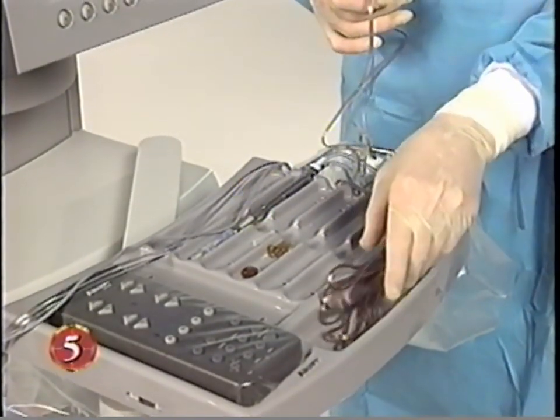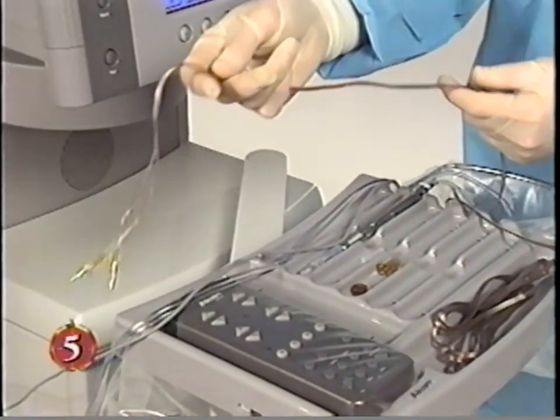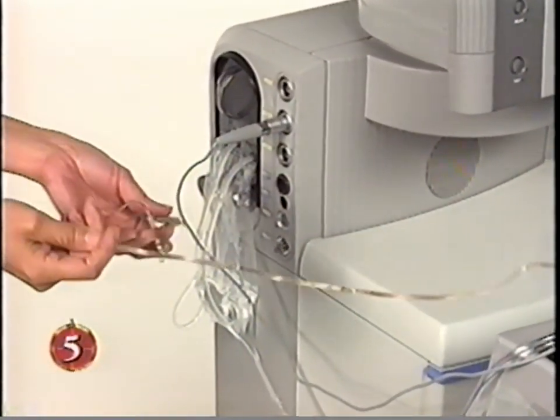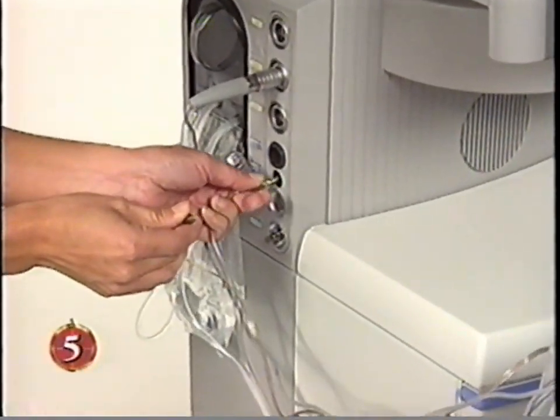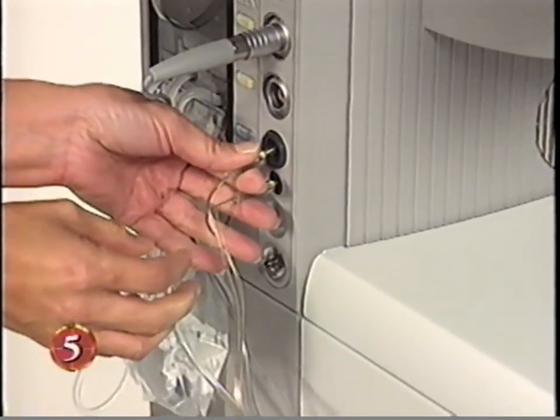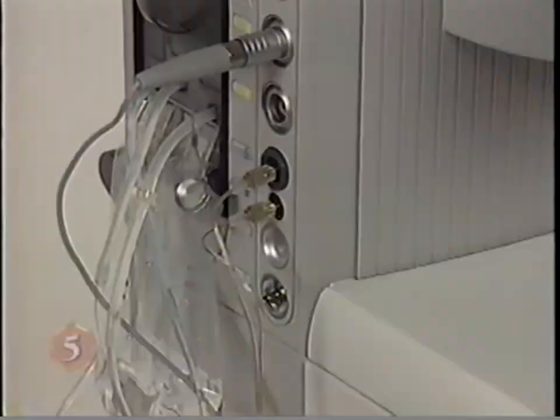To set up the coagulation handpieces or forceps, hand off the coagulation cable to the circulator, who inserts the cable connectors into the coagulation plugs on the Legacy connector panel.